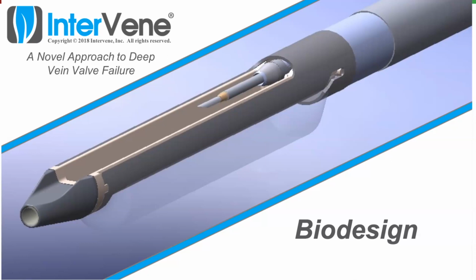So design control is essentially a recipe for your product. You have to write down how you make the product, what goes into it, what gets added when, who touches it, how you sterilize it, all the details so that you could pass it on to a new owner and they could take that recipe and make your product exactly the same.